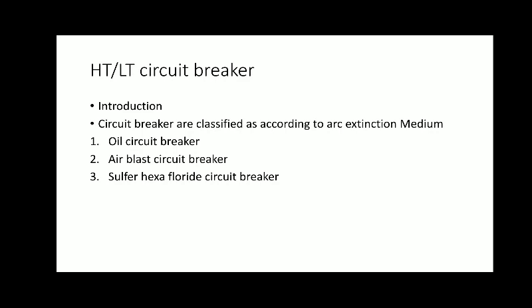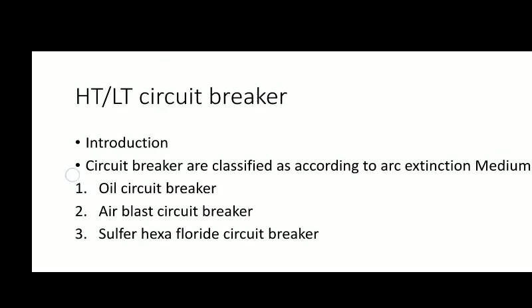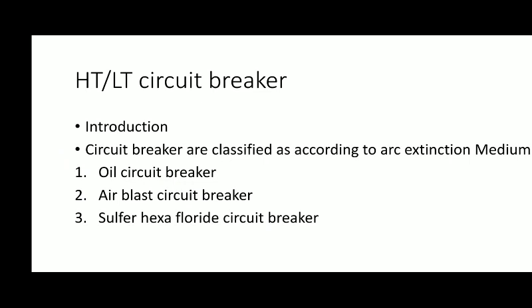First one type is an oil circuit breaker. Why? Because the arc quenching medium is oil, that is transformer oil. Next one, air blast circuit breaker, in which air is utilized to extinguish the arc. Next one, sulfur hexafluoride circuit breaker. What is sulfur hexafluoride? It is SF6 gas. Sulfur hexafluoride gas आहे and it is used for the arc quenching purpose. So these three are maximally used for arc quenching in circuit breakers.